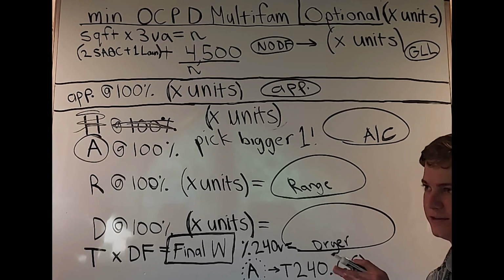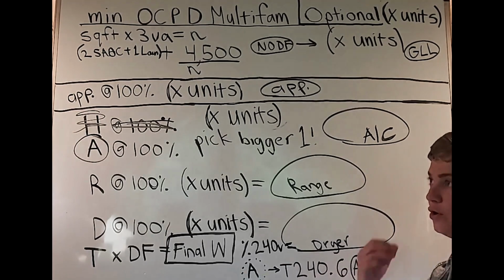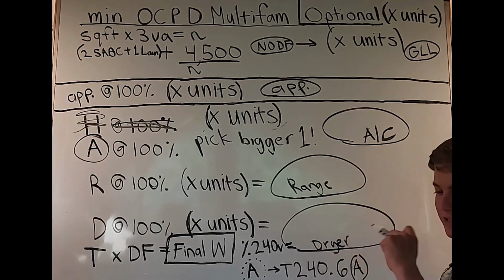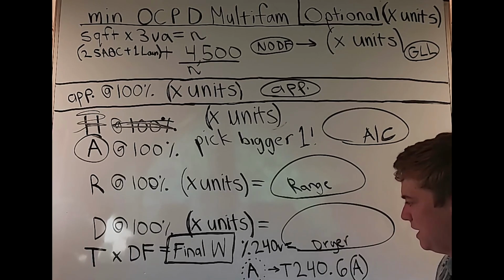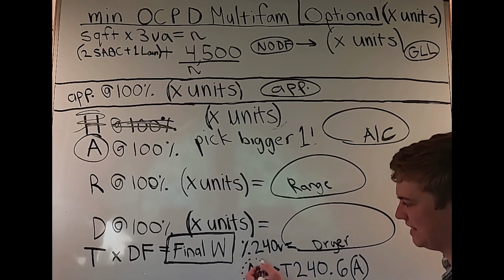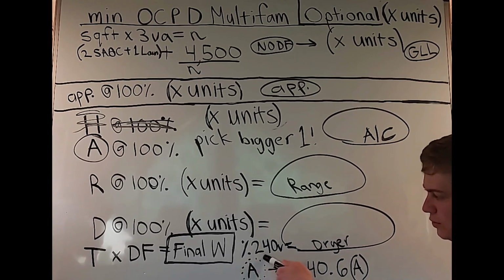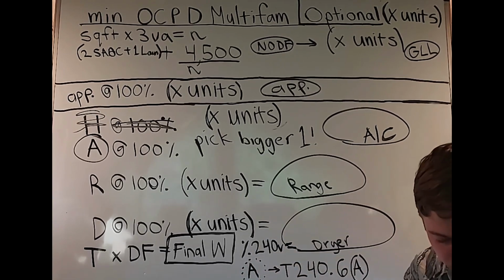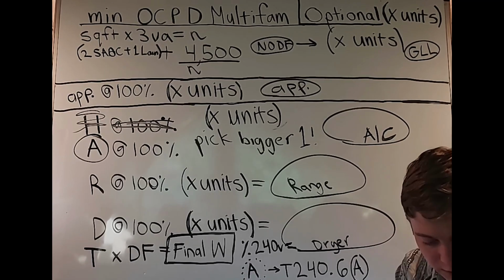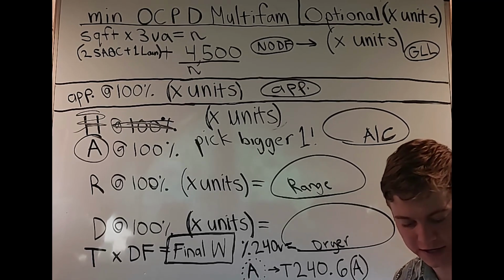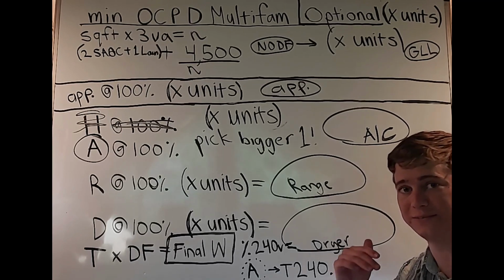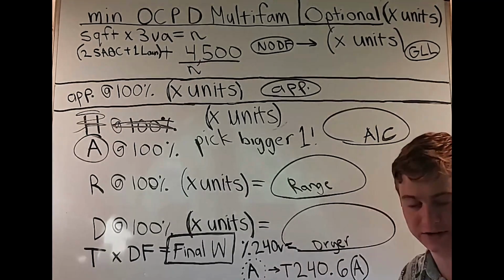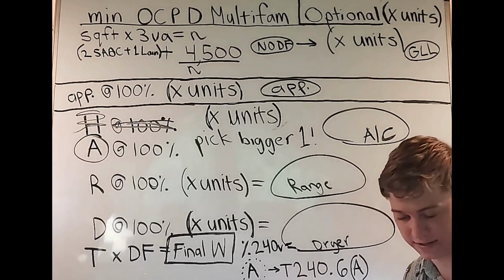And in that case, if we're in the middle of two numbers and we're over 800 amps, we're actually going to size down. So let's look at table 240.6a. If we ended up with 760 amps after dividing by 240 volts, we'd go to table 240.6a, of course, and we see 700 and 800. Okay, so that's in the middle of both of those. And in that case, we're actually going to round up to 800 because we can round up to 800 or less. And that's the limit.